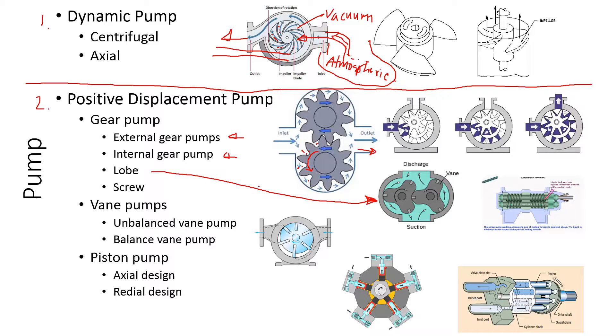The screw pump similarly traps fluid inside the screw grooves and pumps it through. The vane pump works the same way — instead of gears, you have vanes. Because of the rotational motion, when this thing rotates, the vanes extend outward due to centrifugal action. The vane width is labeled L. Fluid coming in is trapped between the vanes and pushed out — it's also a positive displacement pump.